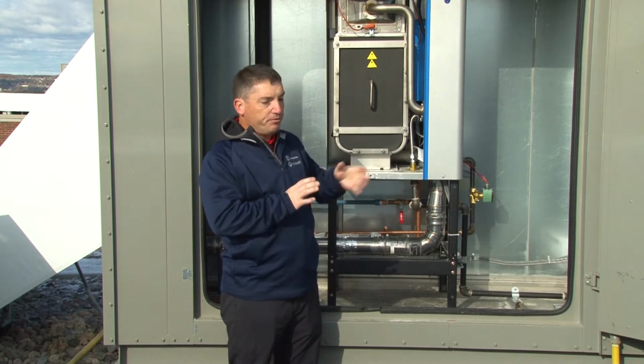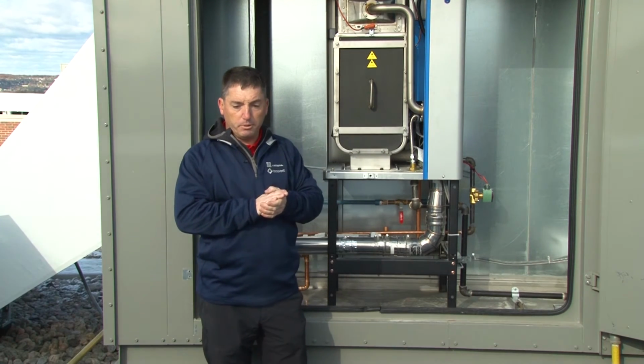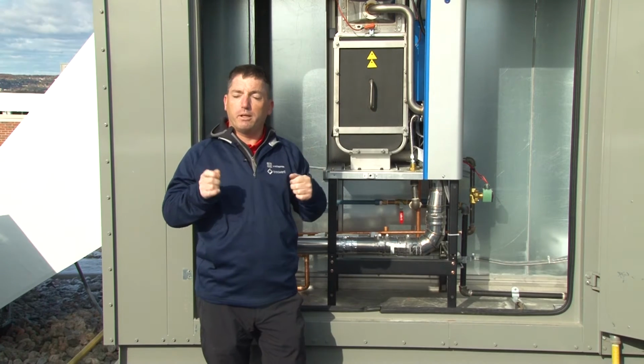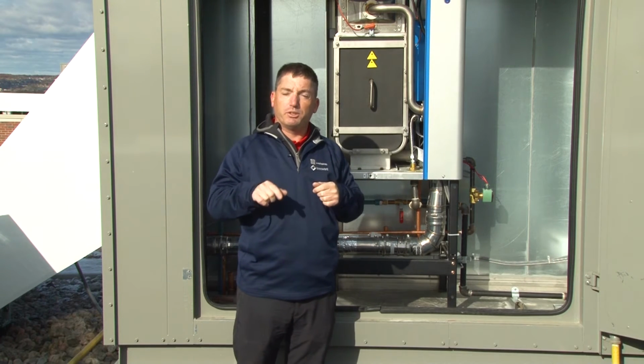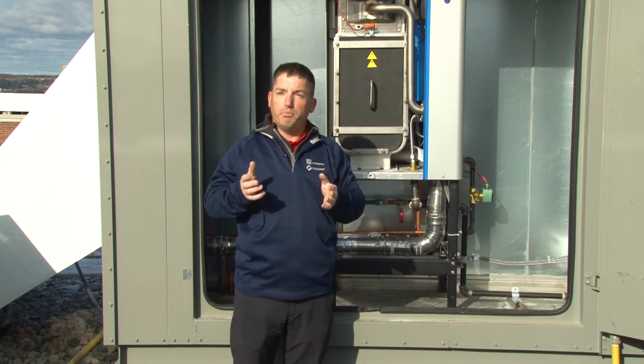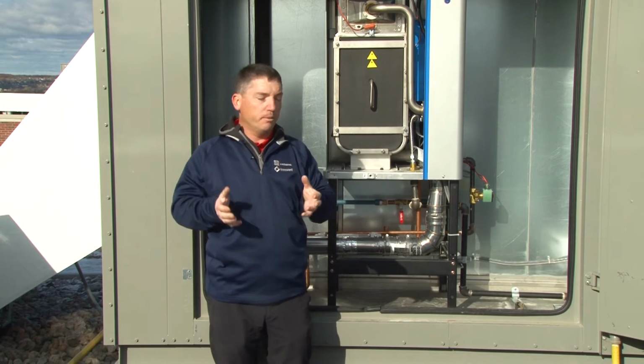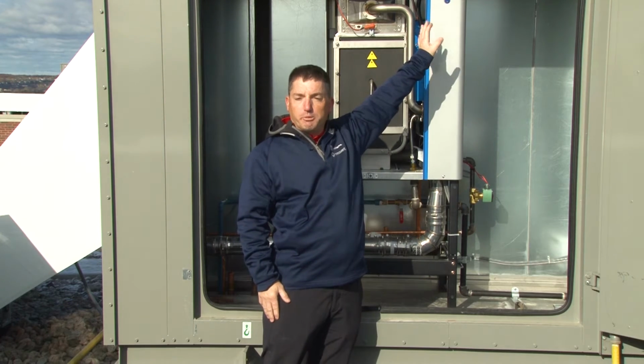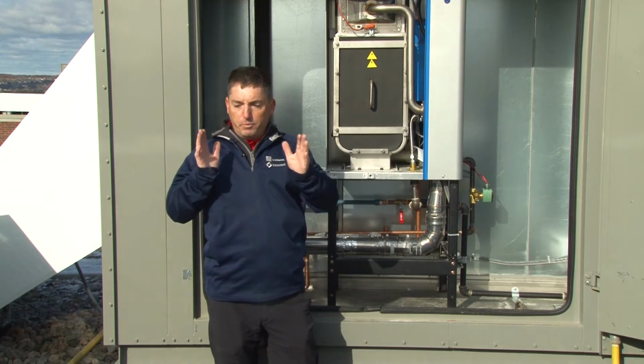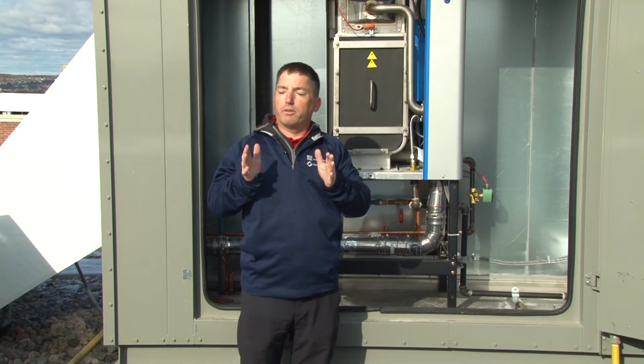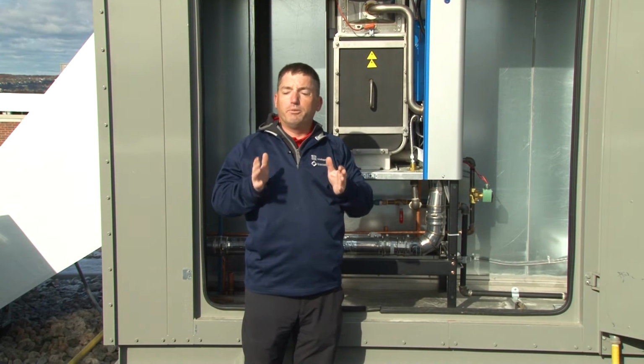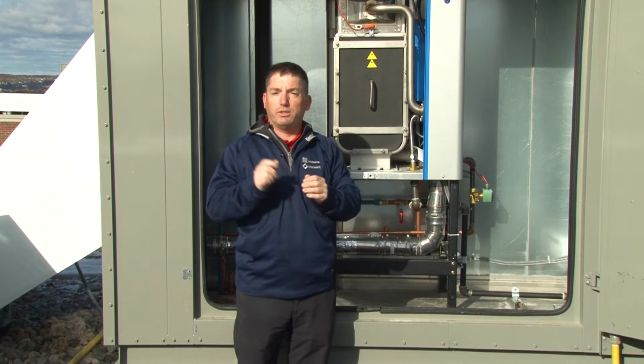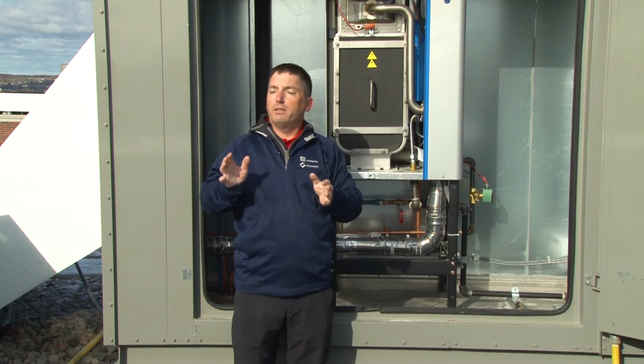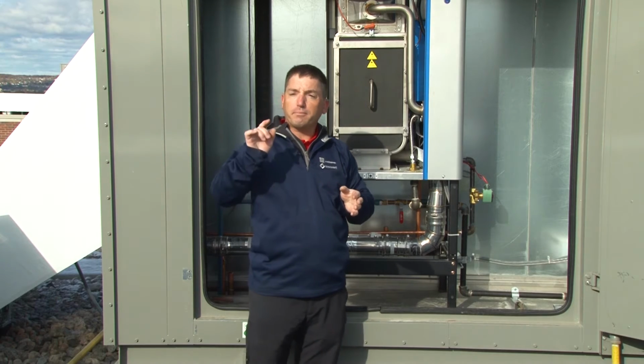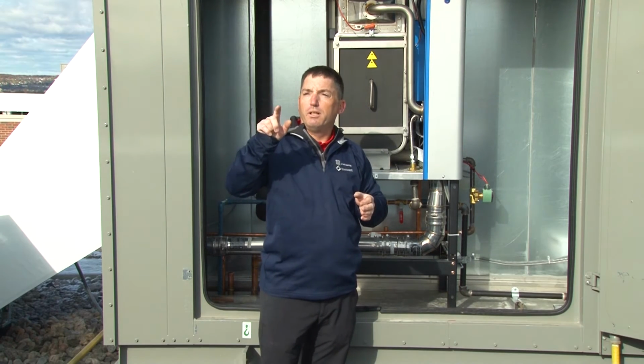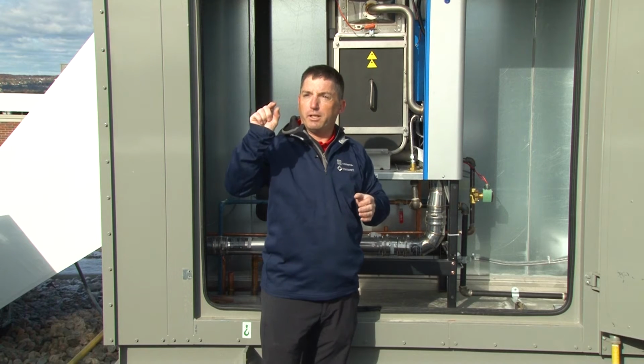If there is a fault, you will get an indication. There will be an error code that comes up on the keypad downstairs that is going to indicate an issue with the humidifier. That's kind of a general alarm. When you come up to the display, the Nortec unit is going to have an error code. One really nice thing about the Nortec units is you don't need to have a physical copy of the manual. You walk up to the unit, you press on the part of the screen that has the error code.